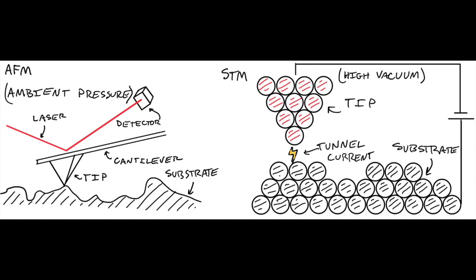Although an AFM is a simpler technique, it actually requires a lot more skill. I always, when I was in grad school, got a friend to do it because I didn't have the dexterity to manipulate the AFM tip and pull it out of its little house when you get one that's new. Anyway, this tip gets scanned across the surface and you shine a laser on top and it strikes a detector to generate an image. It can be used in contact mode or more commonly tapping mode, which keeps the tip at a fixed average distance while it taps out the surface and doesn't quite touch the surface, but it does measure things like topography and polarizability or is affected by electrostatic properties.